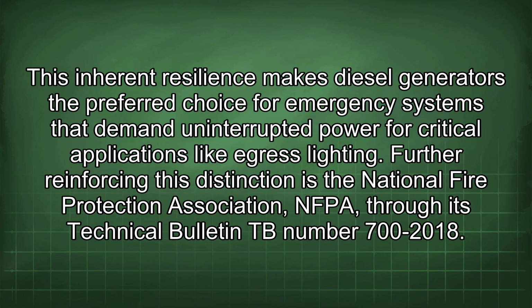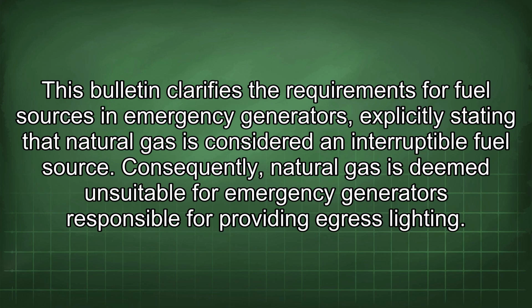Further reinforcing this distinction is the National Fire Protection Association, NFPA, through its Technical Bulletin TB No. 700-2018. This bulletin clarifies the requirements for fuel sources in emergency generators, explicitly stating that natural gas is considered an interruptible fuel source. Consequently, natural gas is deemed unsuitable for emergency generators responsible for providing egress lighting.